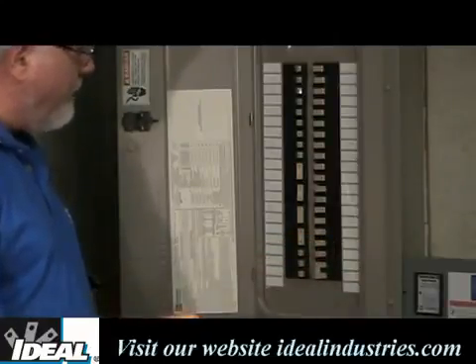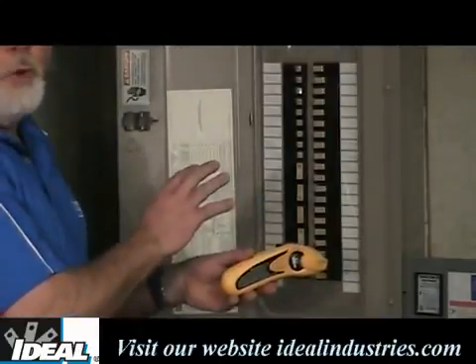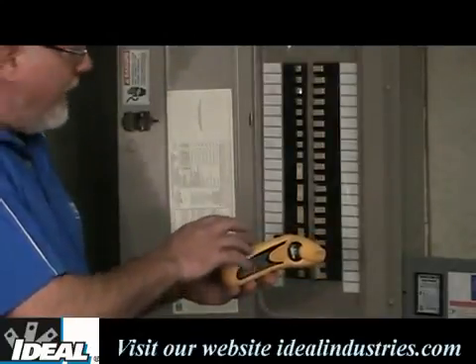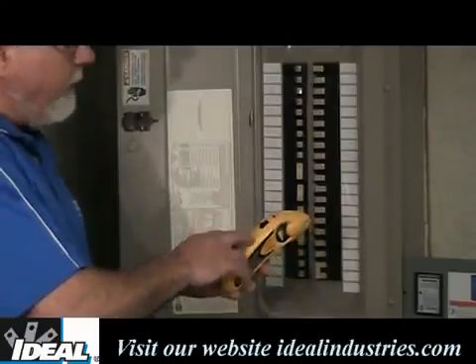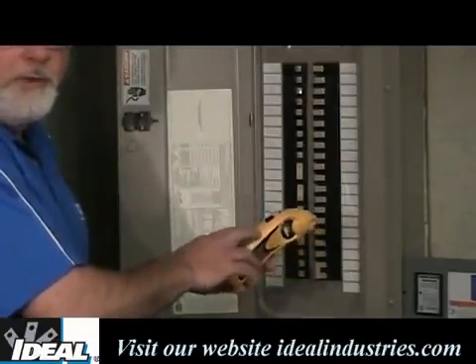Then, of course, we can turn that breaker off and go work on that circuit out in the room. That's how we trace wires with these circuit breaker finders back inside the panel.